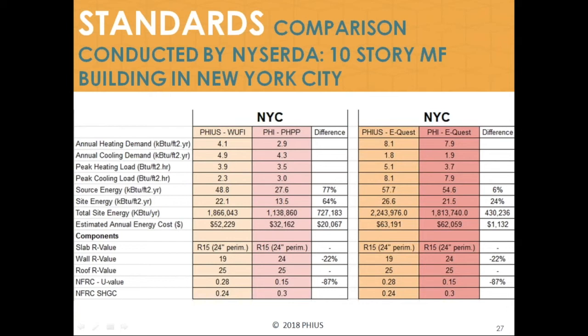The difference in envelope - the bigger the building gets, granted, the difference in terms of additional insulation needed for the envelope is not as big as the 10-unit project I showed you earlier, where the difference in investment was significant. For this big building, you can see that PHIUS standards arrive at an R value in the wall of about 19, and the PHI standards arrive at a wall assembly of about 24. So roughly an inch and a half difference in insulation, but the big difference is actually in the U value for the window.